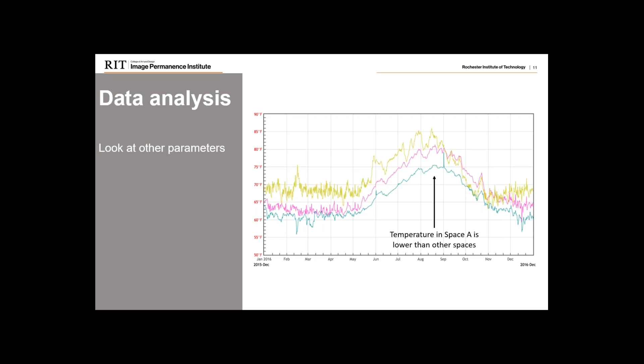So this is just an example of how, when walking through the data analysis, even just looking at the data, we have a sense of what the problem is. It's not necessarily that there's a moisture load in the space itself, or that something is broken on the unit serving this room only. It seems that in general the spaces are receiving the same conditioned air, but the temperature difference is what's causing the relative humidity difference. So that concludes just one example of how data analysis can inform us about the problem. We're going to move into mechanical and space evaluations next and go over some other lessons learned from these other examples.